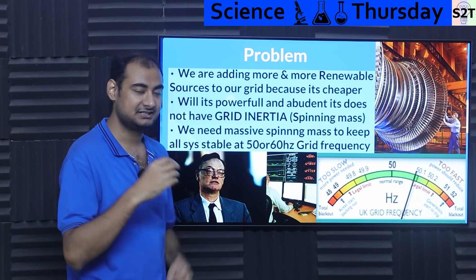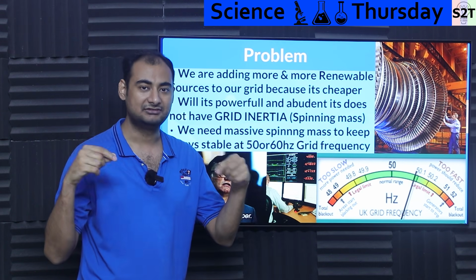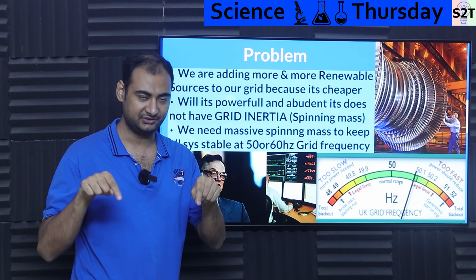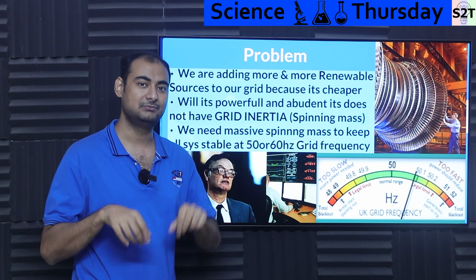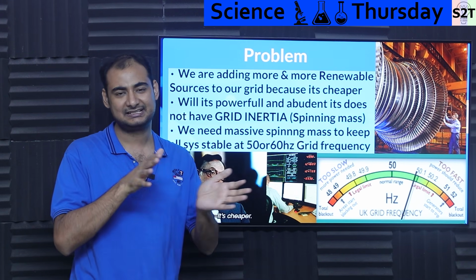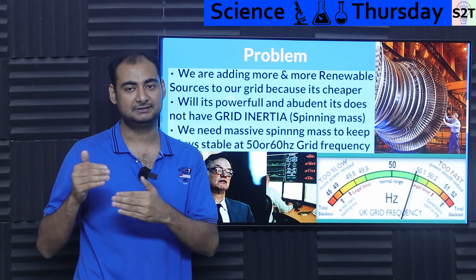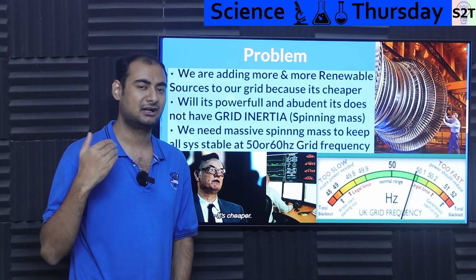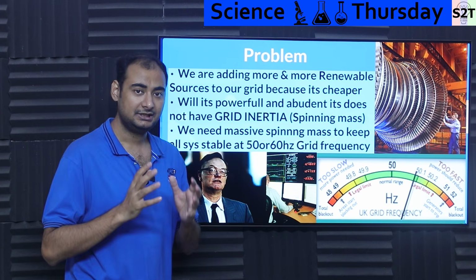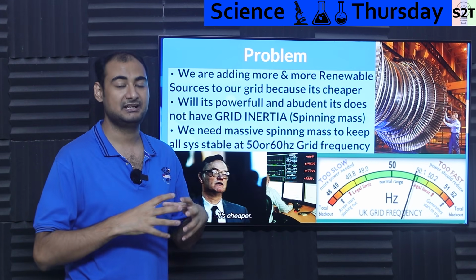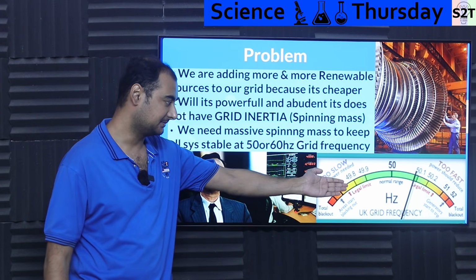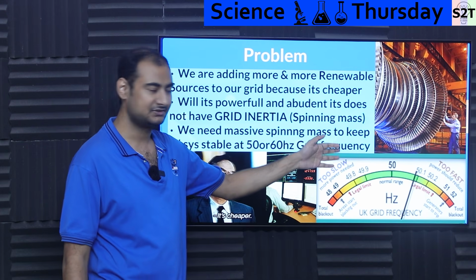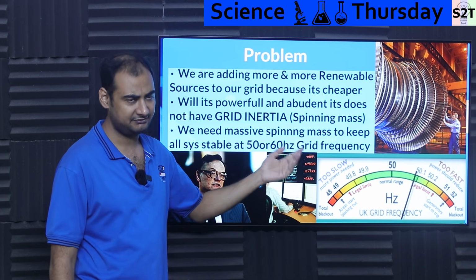There is another variable. Basically, the rotor of the generator has current going into it. That current is generally controlled first, before you control the steam, because steam takes some amount of time to couple, and current in the rotor is far quicker. So that's how we have spinning mass, and that's how we stabilize everything. And this is the key aspect of it. Now, again, if you are in America, put this by 60. Everywhere else, it's 50.